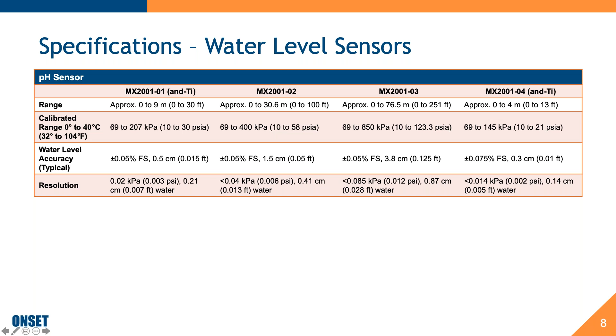The only differences are the calibrated range changes. Other than the range, the water level accuracy is the same for the 0 to 9, 0 to 30, and 0 to 76: plus or minus 0.05% full scale. The smallest range, 0 to 4 meters, is plus or minus 0.075%.